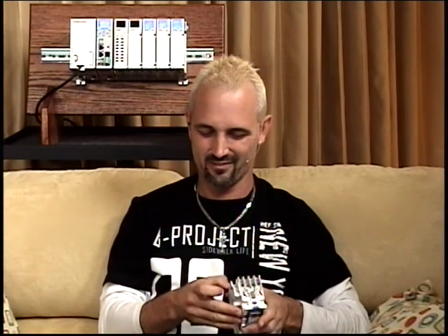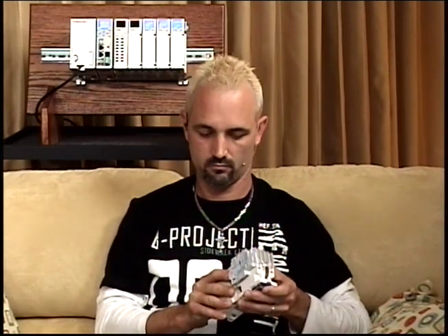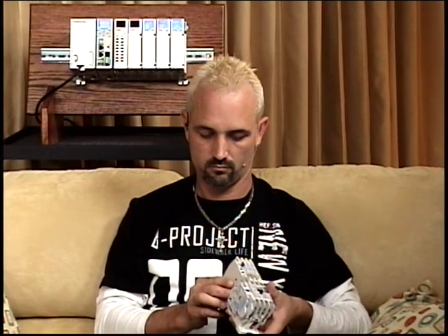So you might have a motor, again, it pulls 11.2 amps, and you're going to buy your heaters based on the application. And these are ambient compensated, and let me explain real quick what that means. A lot of times your motor starter with your overload relay and contactor might be located in a building where it's heated and humidity controlled, whereas the actual motor might be in a pit someplace outside where it's cold and damp.